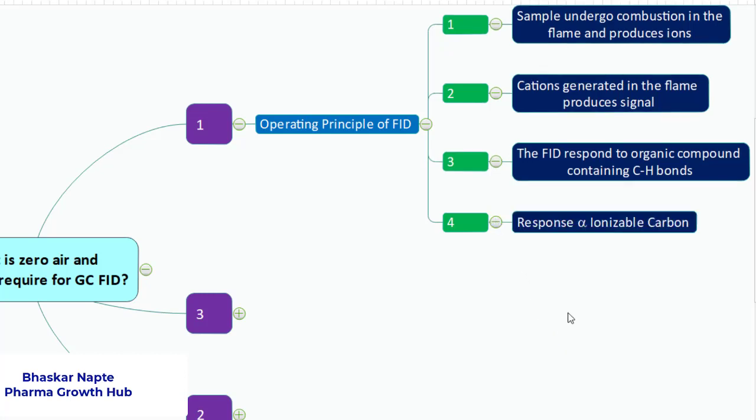And the last point is what is the response of the FID? The response of FID is directly proportional to the ionizable carbon molecules present in a sample. That means if you want to compare the response of methanol and ethanol, which compound will give more response? Obviously ethanol as compared to methanol. Why? Because ethanol contains twice the carbon as compared to methanol. So this is the way the FID works.